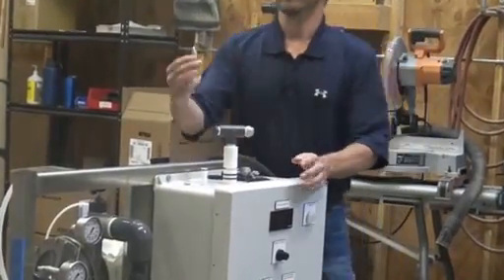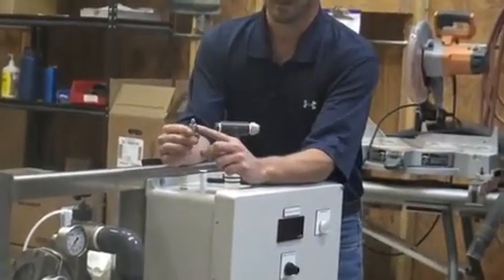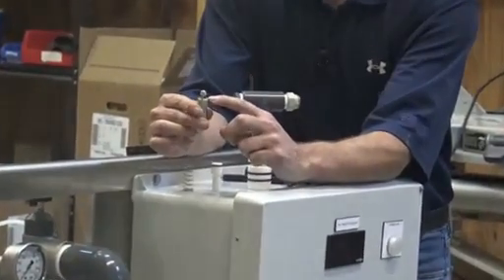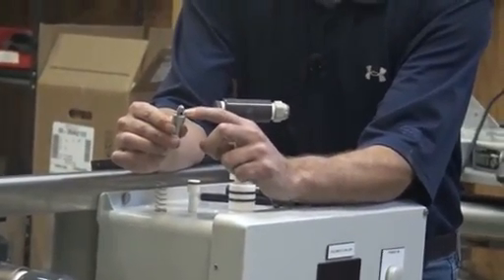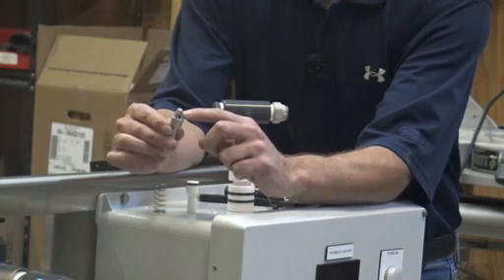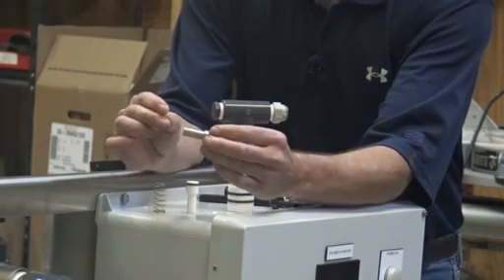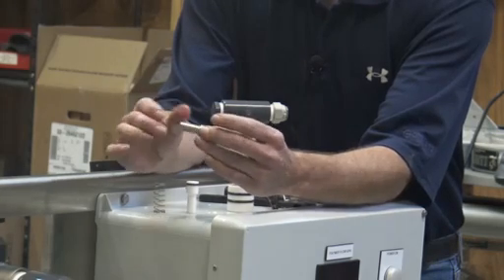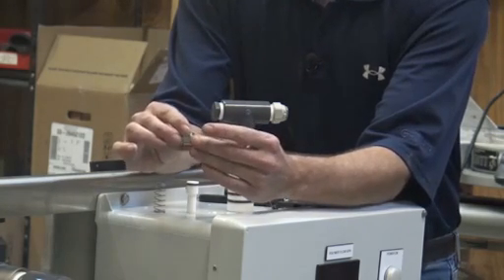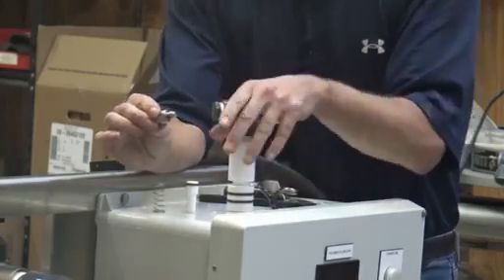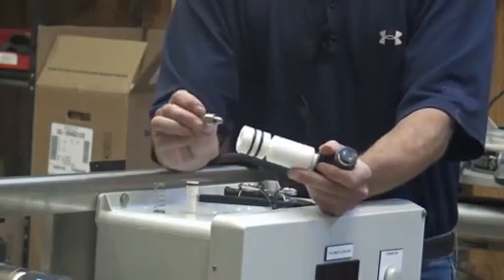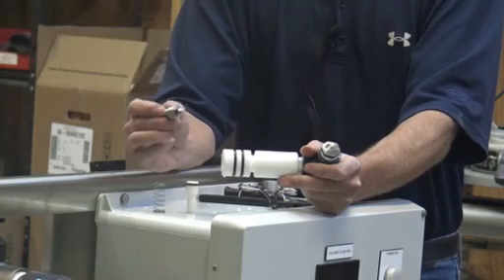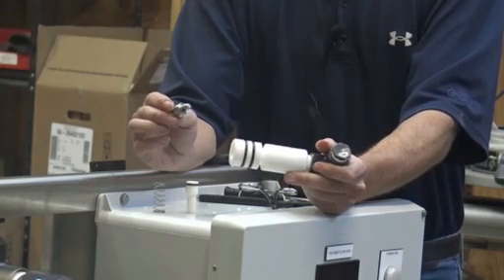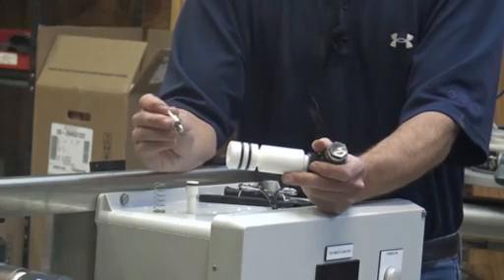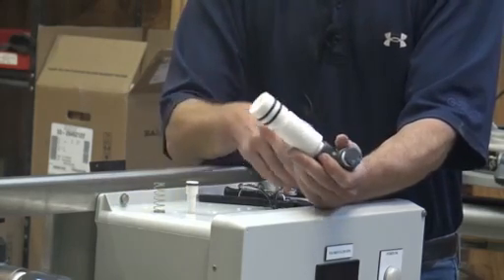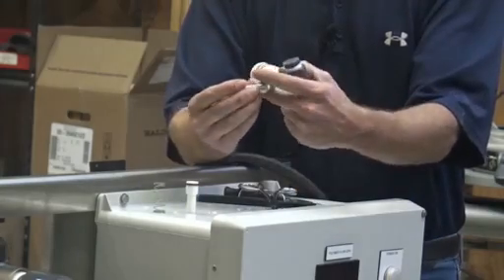The poppet is the most important part to get clean, because you want to make sure that there's no clumping or hardened silicone polymer developing on these two holes here. If there are, you need to really clean it out well. The best way to do that is with hot water. But if you're going to do that with hot water, you need to make sure when you put this back together, it is completely dry. What we like to do is let it sit overnight and naturally dry. You can use compressed air to do this also by blowing into the assembly and blowing this all completely dry.